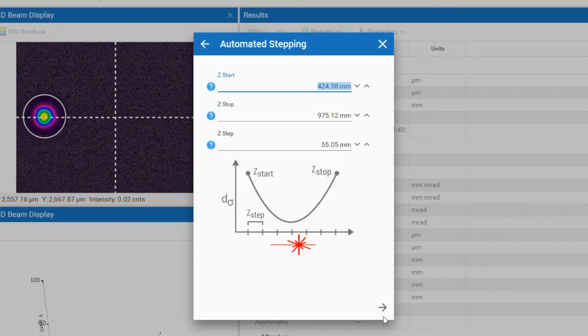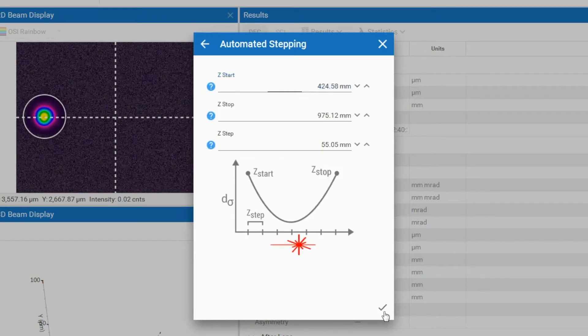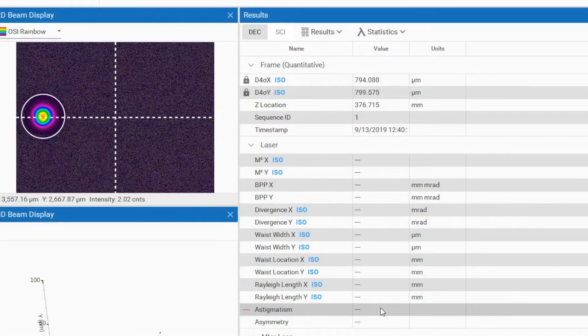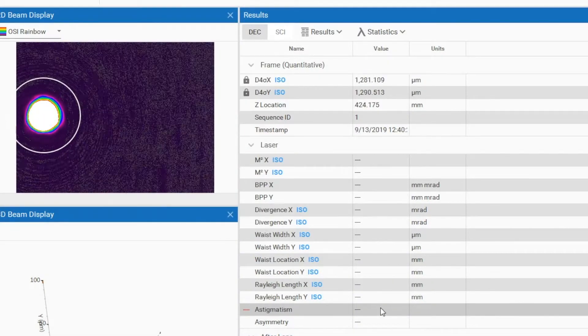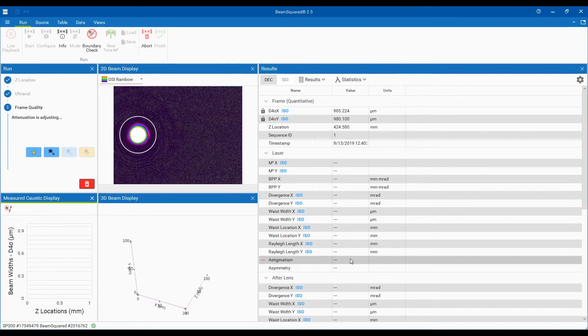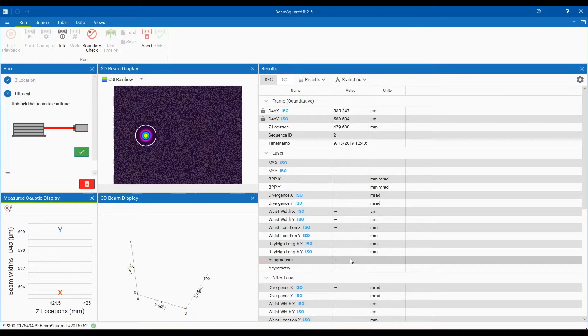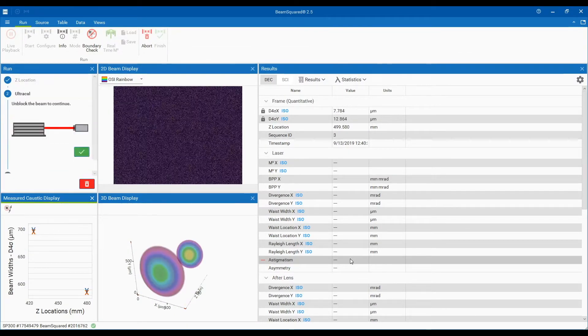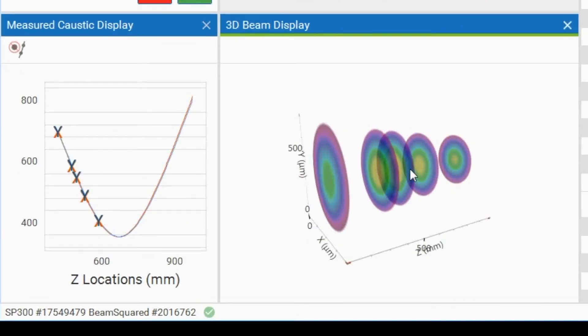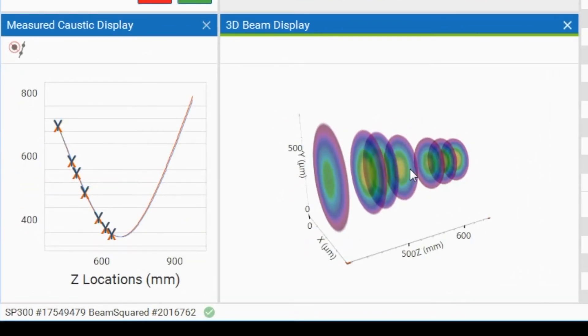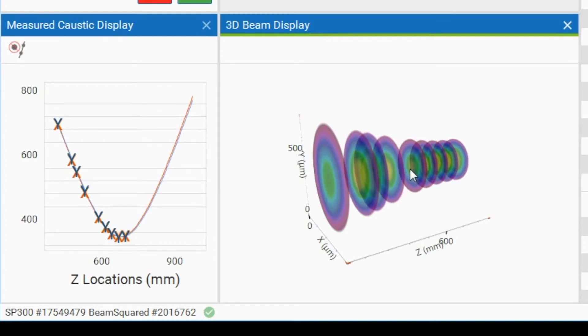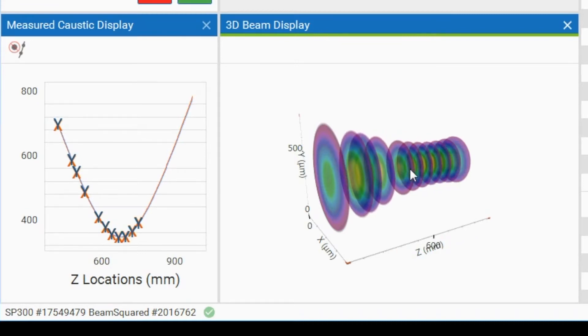The automated stepping mode only requires a start and stop location and a step size. The Beam Squared will then start collecting measurements at the first Z location and proceed to make additional measurements at every step. This method may also produce a measurement that satisfies the ISO standard, but the start, stop, and step size parameters may need to be modified depending on the Rayleigh range of the laser under test and the lens that is selected.